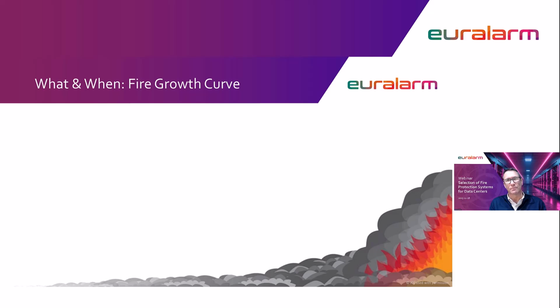Detection can also mean, if we have a glass bulb that is thermally operated, think sprinkler head or water mist nozzle, and if the purpose of the airflow, the air conditioning, the cooling, is to strip heat from a processor to prevent it overheating and it suffering thermal damage, we have a conundrum where the same airflow will impact any fire development from operating a thermal bulb.